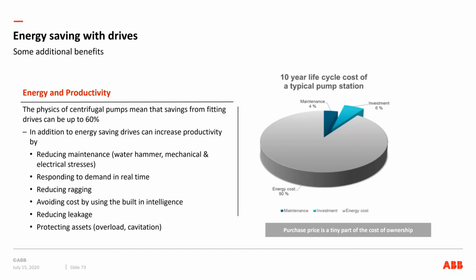A wipe can last a while, and what happens is that it builds up on the pumps, on the impellers, along with strings, debris, and rags, all those things we're flushing down toilets that we shouldn't be, and that builds up on the pumps. Today, drives have features in them, like we have pump clean.